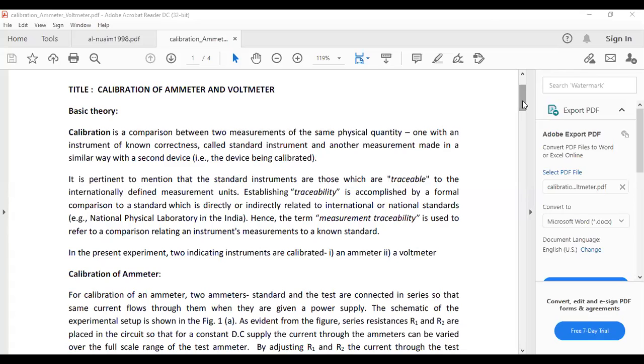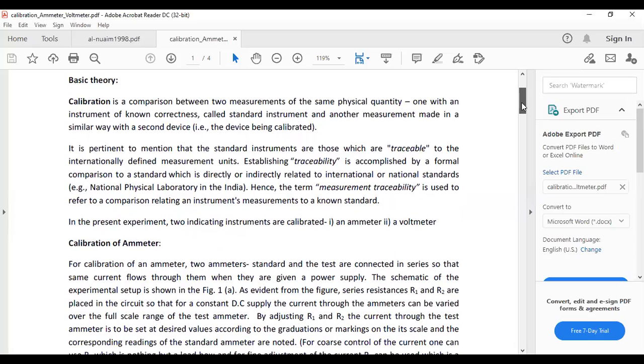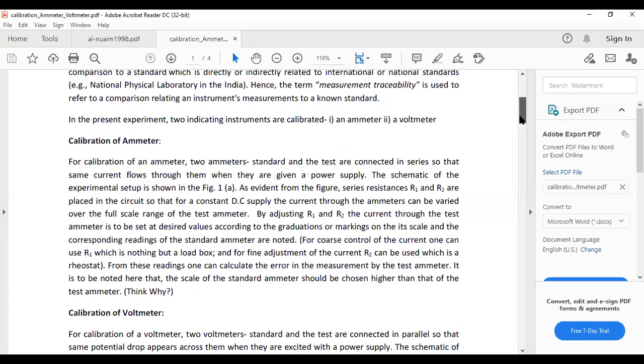Okay, suppose the ammeter is 0 to 10 ampere. Now for all this scale, that means 1 ampere, 2 ampere, 3 ampere, up to 10 ampere, for all these readings, we'll check how much error it shows with respect to the standard ammeter. So this is how we calibrate the ammeter, and the same we do for the voltmeter as well.